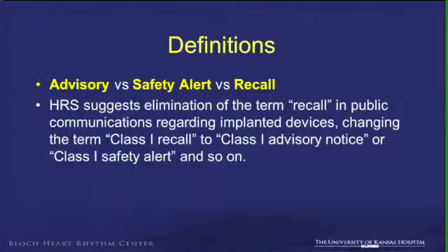Now, I want to just go over the terms which we come across: advisory, safety alert, and recall. They all mean the same, essentially. They're used in different forms, and recall is the common term used by the industry, and in other industries like a car auto manufacturer, where when there is a recall, you essentially replace the part or the device. But that doesn't hold the same for EP, where if it's a recall, it's an advisory, and you still have to do a lot of processing on whether that device needs to be exchanged or not. So we keep mixing advisory, safety alert, and recall.